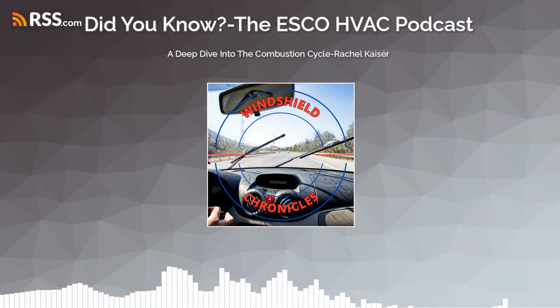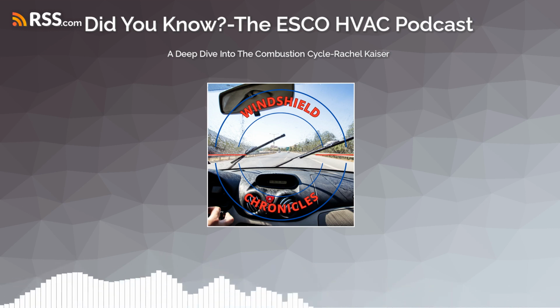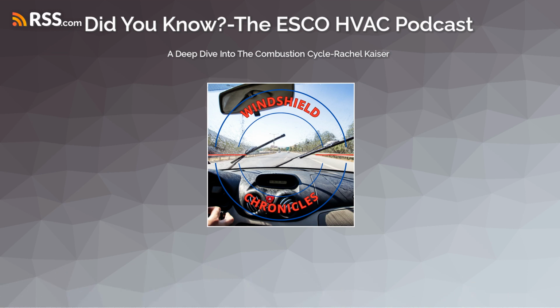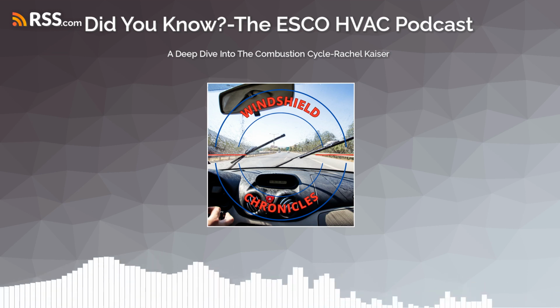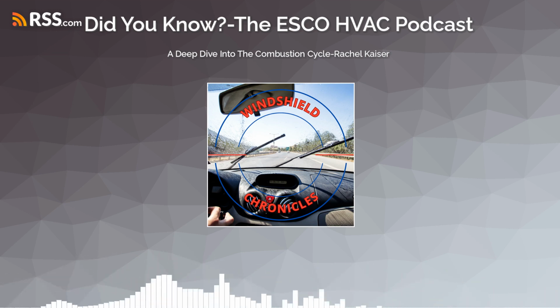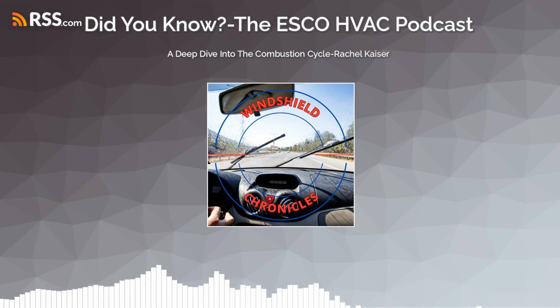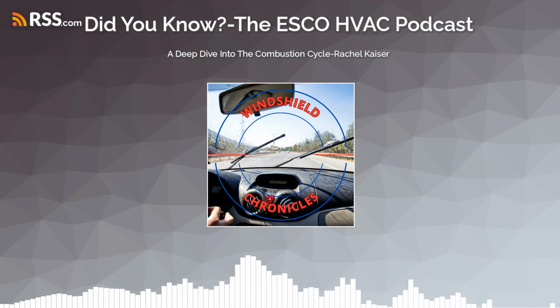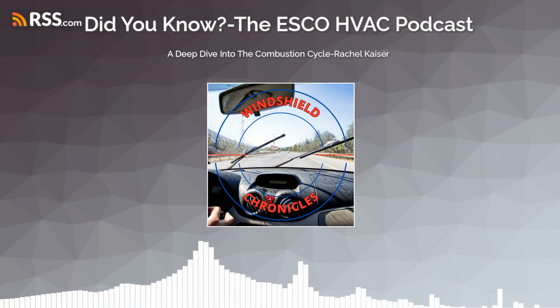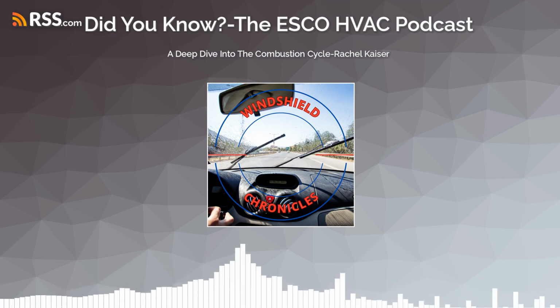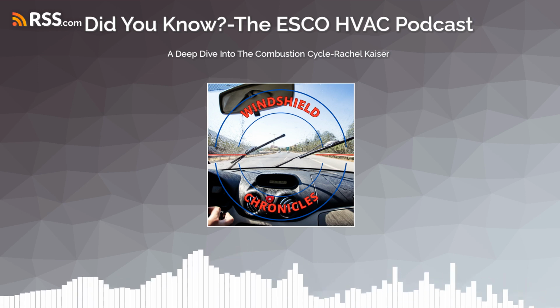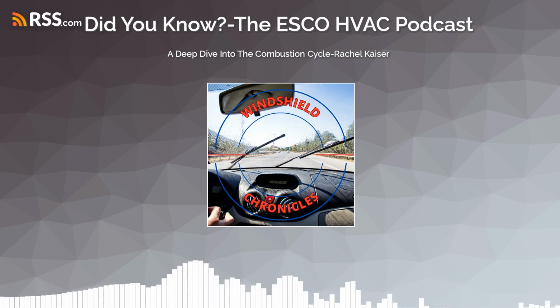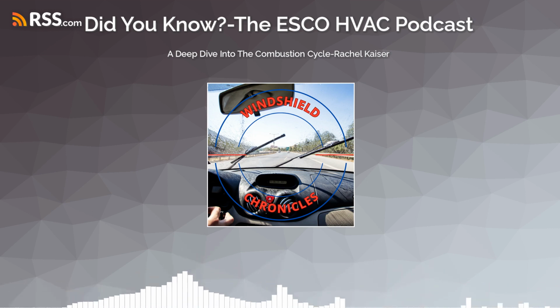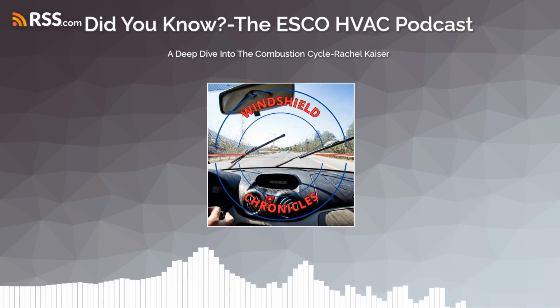Wow. I've always promoted the use of dual pipe installations for high efficiency gas furnaces. I've always been a big proponent of that and been against using single pipe systems and using your interior air for your combustion and for the efficiency of it. But typically I was looking at that from the perspective of utilizing that oxygen-rich outside air. Now that I look at it again, even more importantly, it's to remove the combustion air from the contaminations of the indoor environment. And that's a fascinating point, Clifton, because we do that even in those direct vent situations where you have those two pipes and you're doing the best that you can, thinking, hey, I'm going outside and getting fresh air for this combustion process. It's controlled in a much better way than randomly pulling air from whatever room that appliance is in.